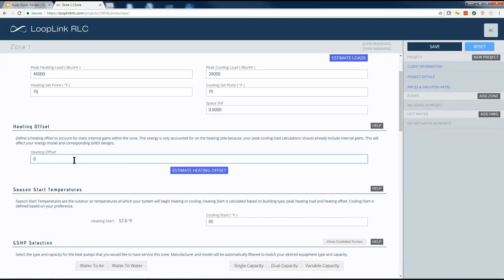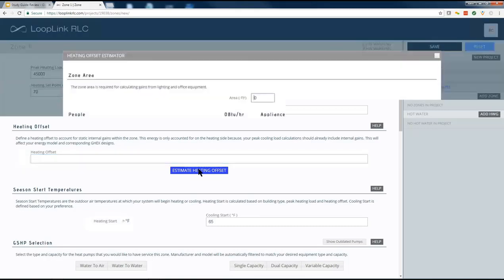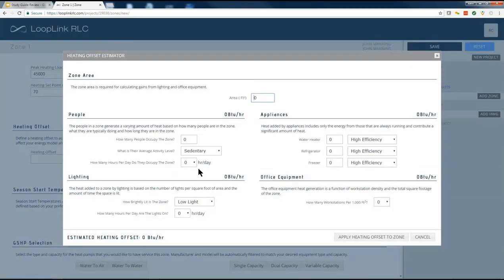What you want to do is try to account for normally occurring internal heat generation, right? So if you know a value for that, you can put it in directly. But if you don't know a value, we've got a little calculator here. If you click on Estimate Heating Offset, as soon as you do, it'll bring up a little worksheet that you can fill out. And let's just say, for the sake of example, this is a 1,500 square foot house, maybe 4 people living there. Slightly active.